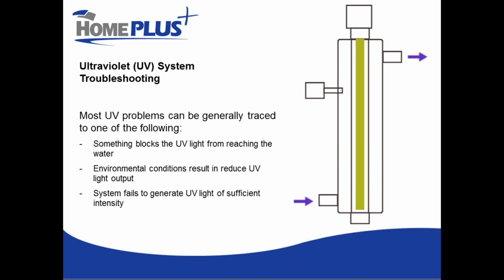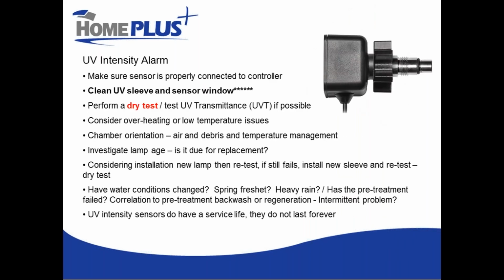So back to my little picture here, we have this sensor on the side of the chamber, and in order for that sensor to say everything is good with my UV system, let's keep producing water, UV light has to get from the lamp through that little pocket of air, through the sleeve, through the water, through the window on the sensor, the little glass screen on the sensor, and then into the sensor itself, where the sensor can capture that reading. So when you have an intensity alarm, something in that process is breaking down. It could be that the UV lamp itself is no longer putting out its proper UV output. As I said, you can consider the age of the lamp, and if it's getting close to its life, it's maybe a little bit more likely to be related to that.